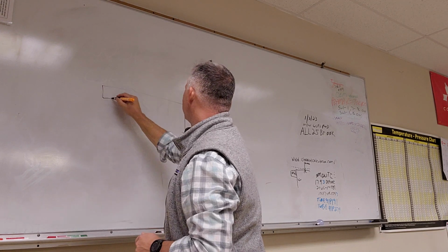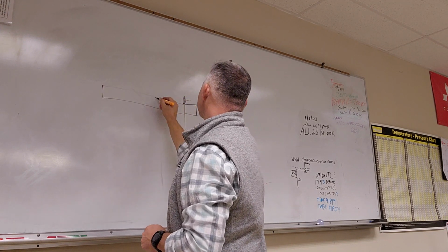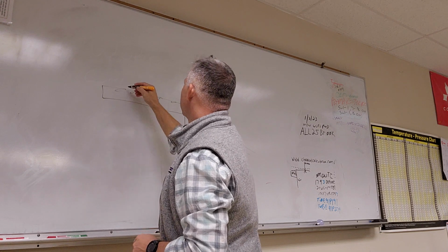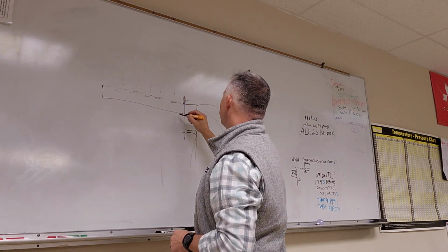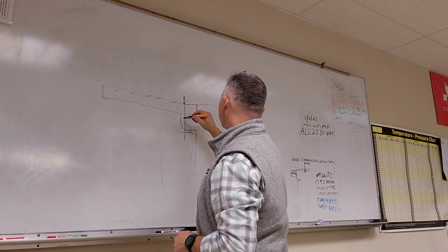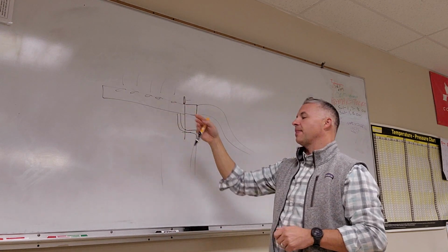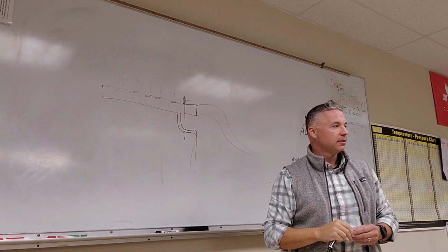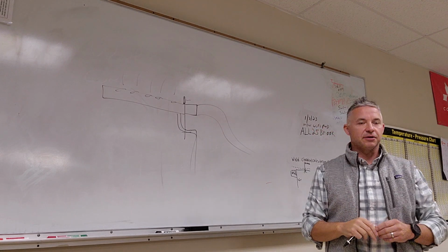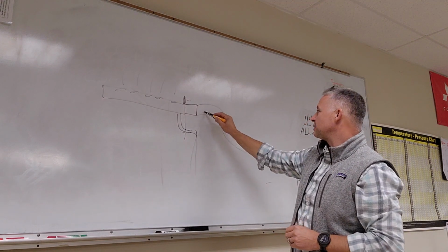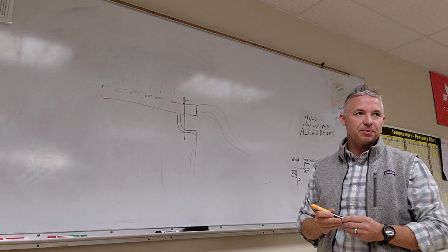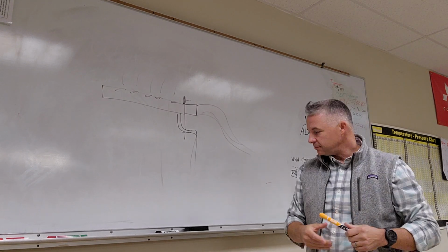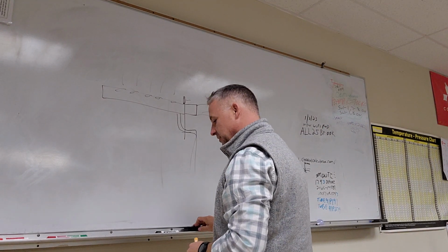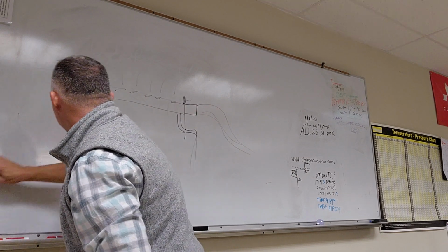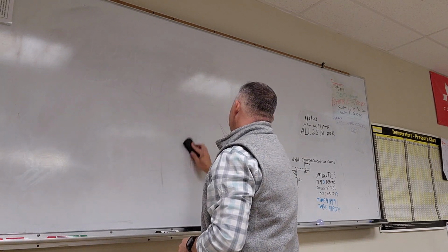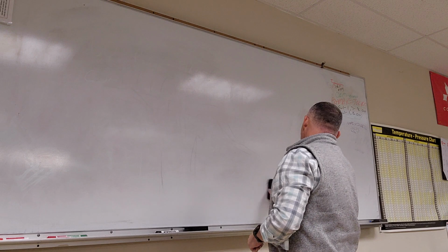There's an actual steam distribution tube, and it has a bunch of holes on the top like AJ was just noting. And the steam drifts out. And that also has some kind of draining element in there. So the pitch on that, you always want to be pitching back. You always want to be pitching all the way back to the steam cylinder because there's condensation happening in the hose too, so that has to be pitched. And if you have water in your ductwork, it makes a mess, and you don't know where it's going. Water is just a big pain because it causes damage and it creates service calls.